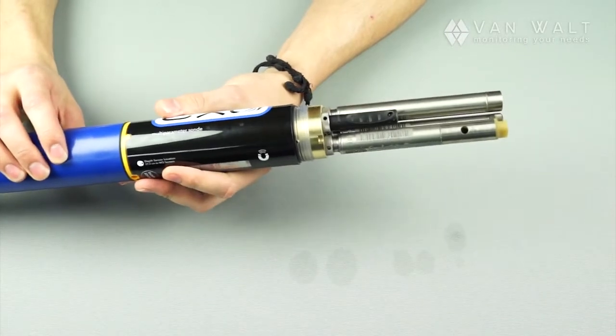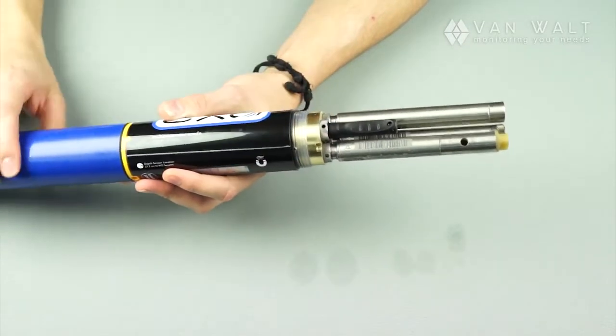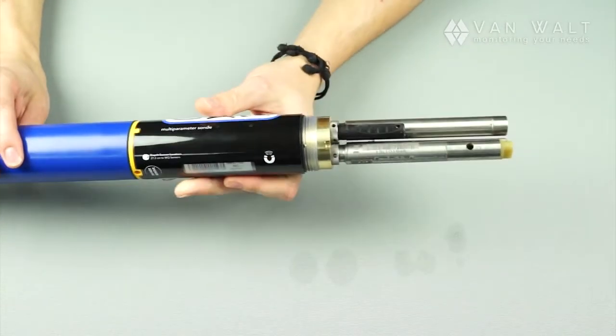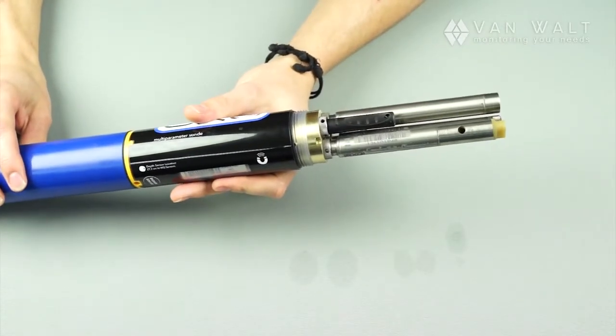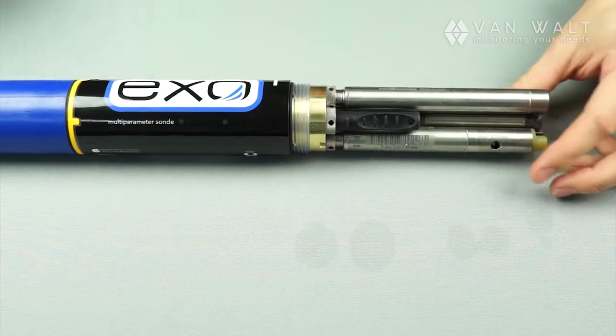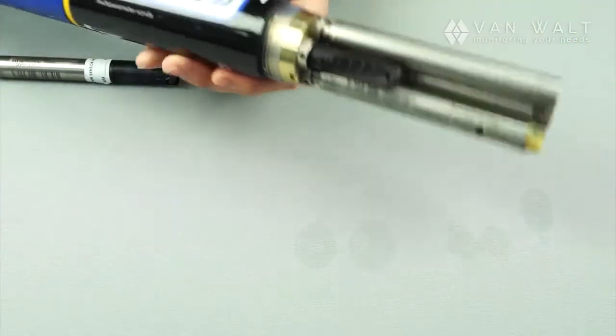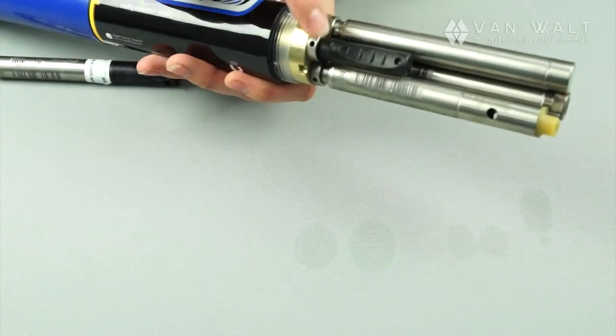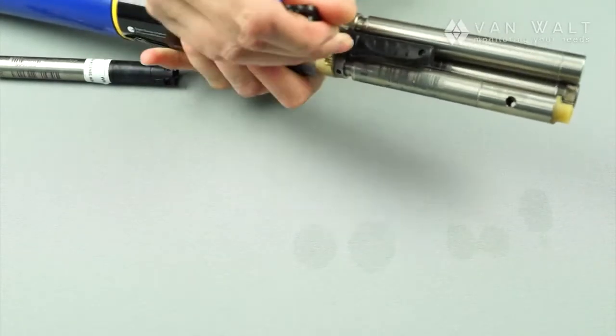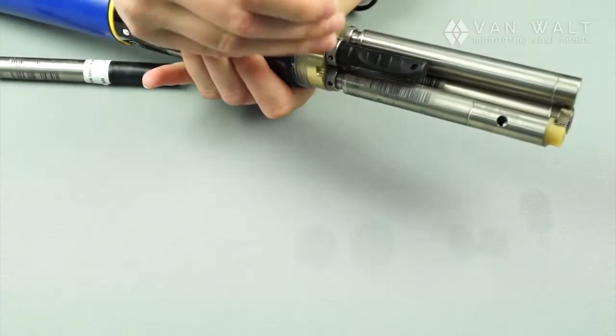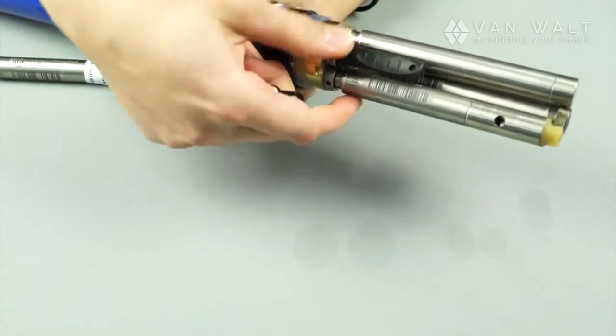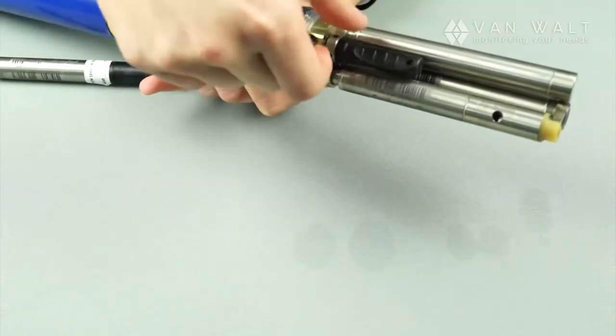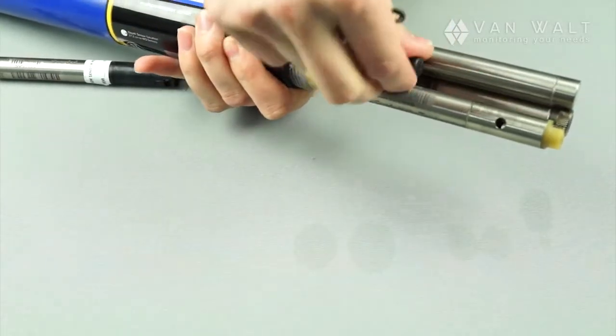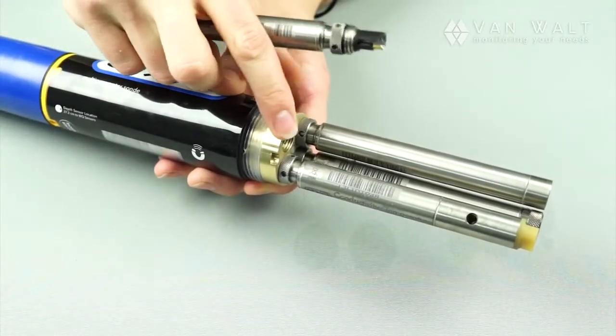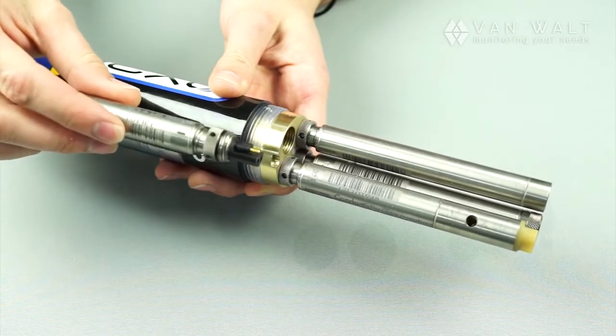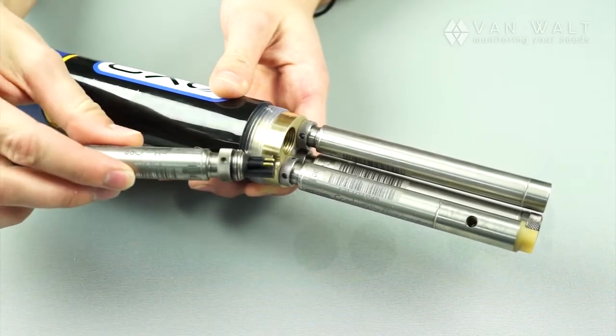There's the addition of wet mateable connectors to increase reliability in the field. This particular unit, the V1, can hold 4 probes. The business end of this logger, there are 4 ports. This at the moment just has a port stopper in. If I remove this quickly, this port here, which had our port stopper in, is actually where our pH and ORP combined electrode would live.